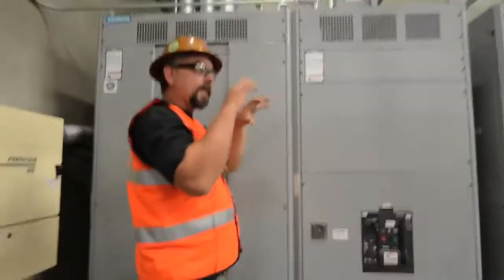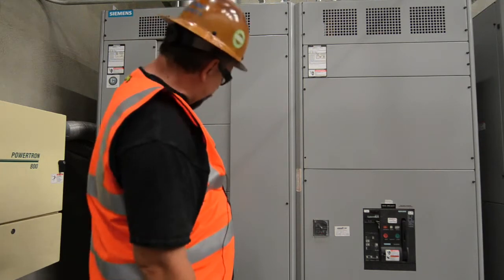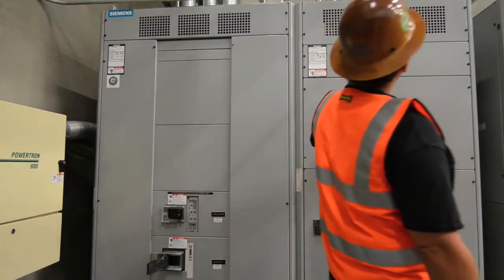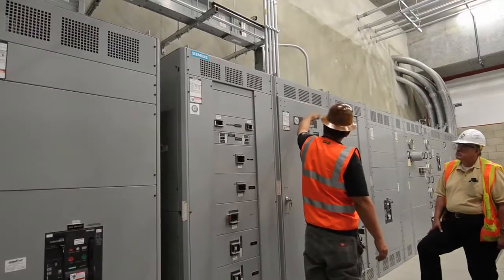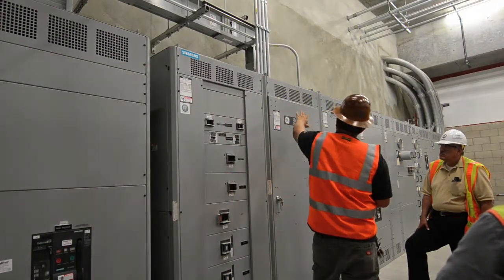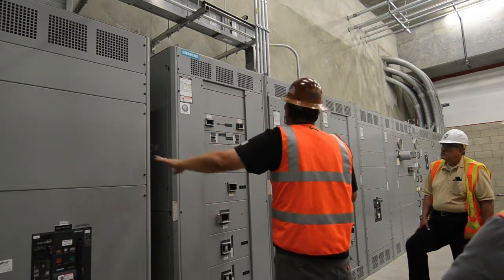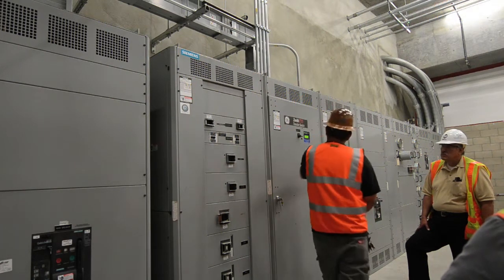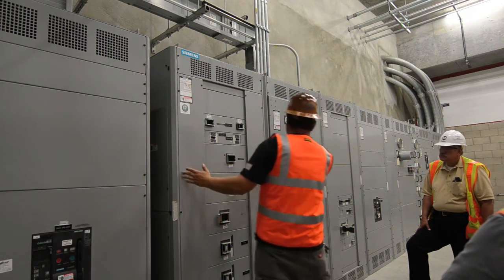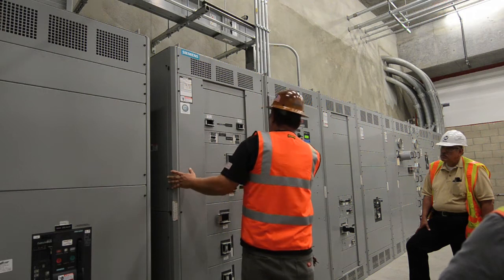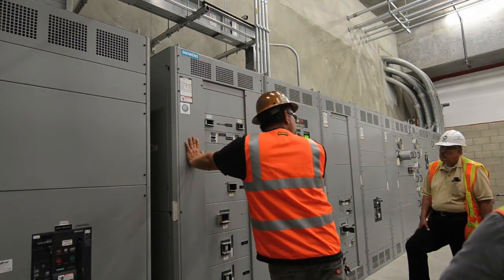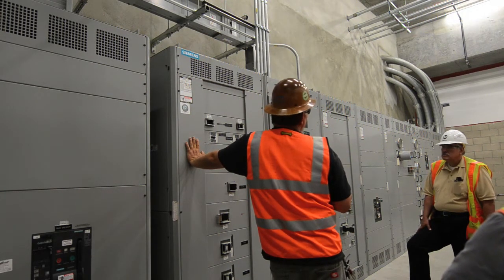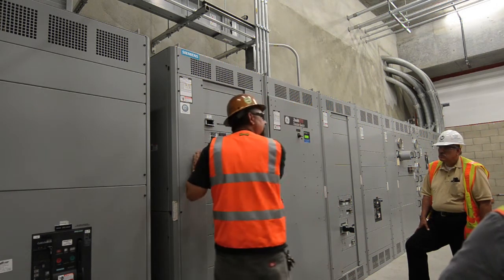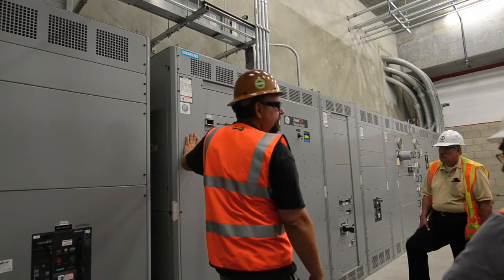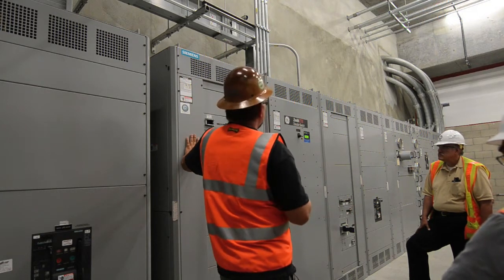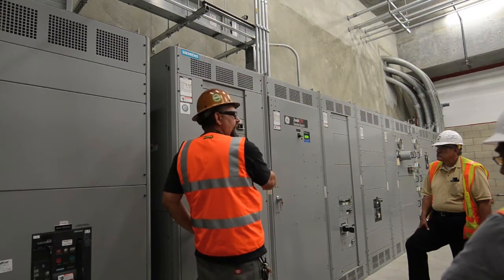They parallel into this switchboard. They go through these two breakers into this main. They leave this main through the bus duct up into the top of the ATS switch, and so that's your emergency system right there to the left of me. From here over, this is all normal power. These loads right here are emergency loads that are fed through the ATS switch with normal power during normal operation. But when normal power is lost, generators fire up, ATS transfers and keeps this board hot on the generator. So this is an emergency switchboard that's running off normal power during normal business. During a power outage, it then is fed off the generators, okay?